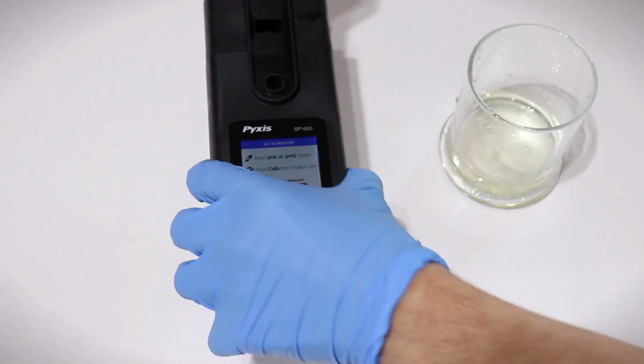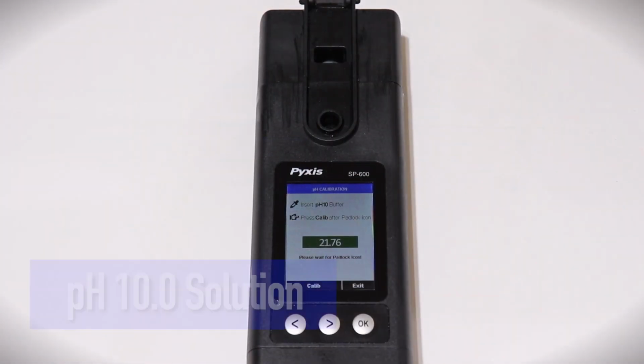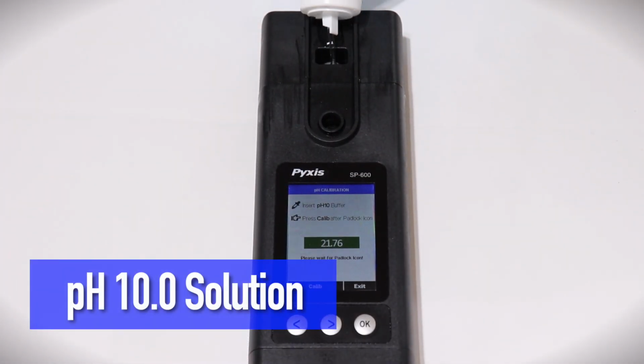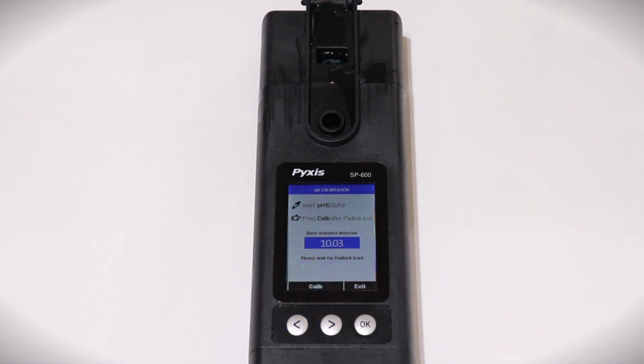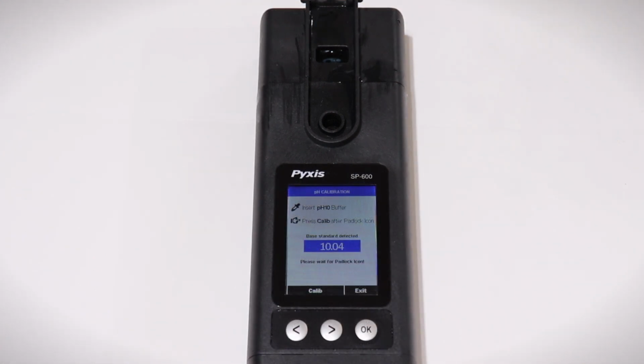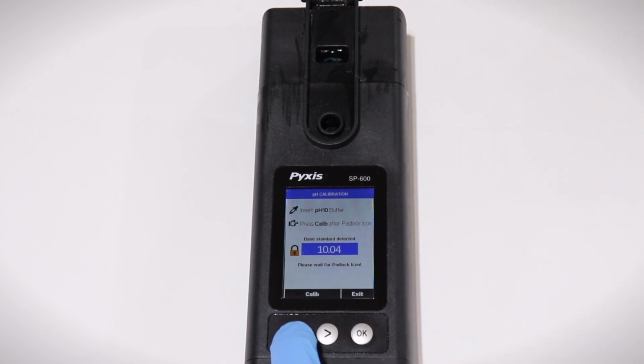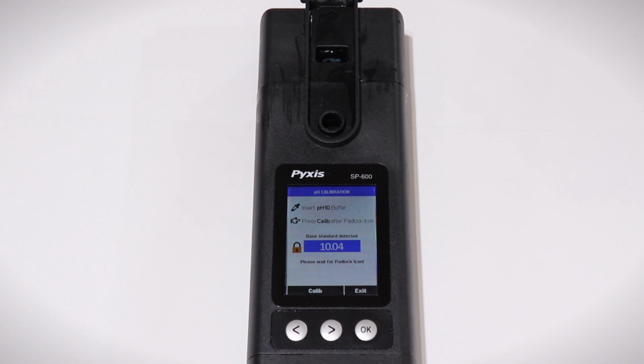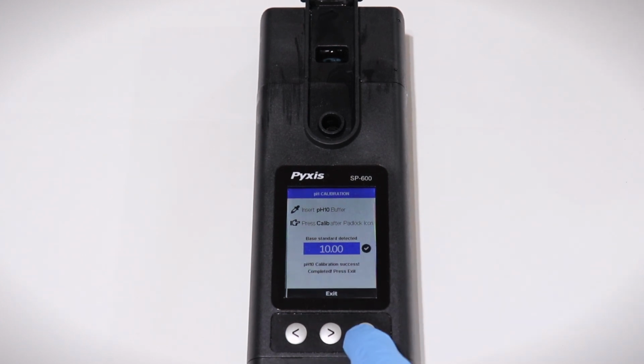Now triple rinse the module with pH 10 calibration solution. Then insert pH 10 calibration solution into the module and wait for the lock icon to appear. Then press either arrow button to select Calibrate. A calibration success message will appear, and your SP-600 is now calibrated for pH.